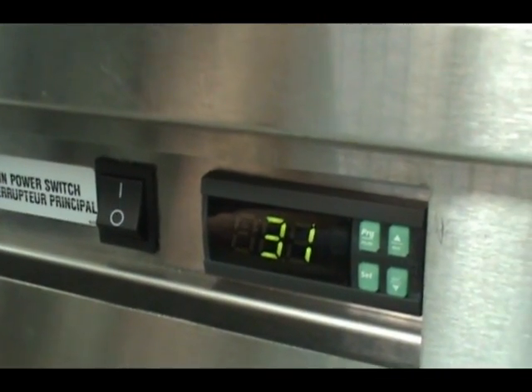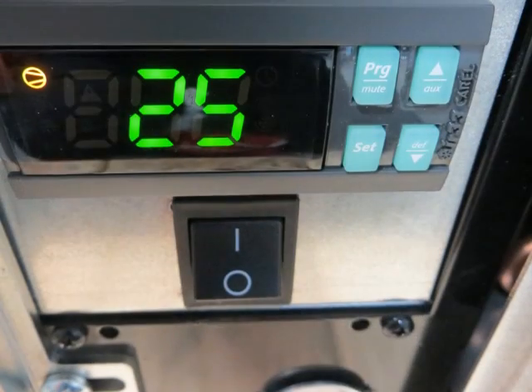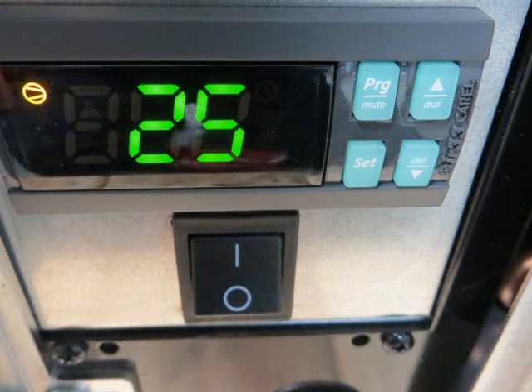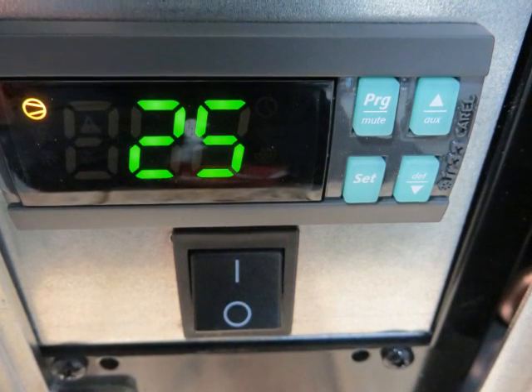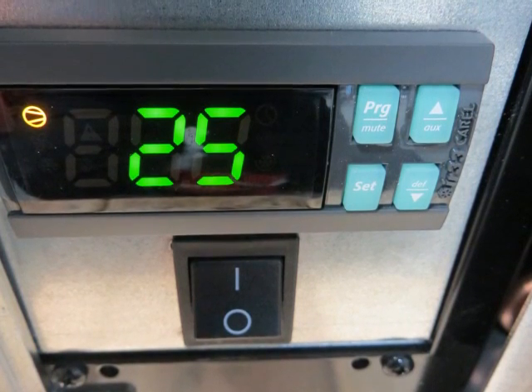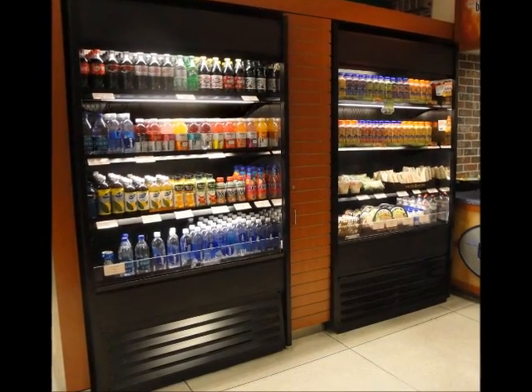Normal operating temps will read in the low to mid 20s. Let the unit run for a minimum of 30 minutes so it comes down to temp before loading your pre-chilled products.